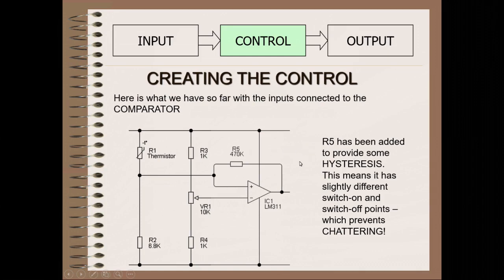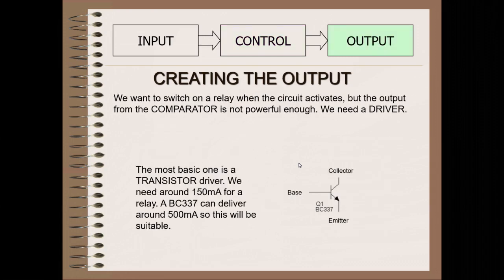R5 has been added to provide for hysteresis. It means that it has slightly different switch on and switch off points to prevent chattering. So if your switch on and switch off points are too close to each other, it would probably rapidly fluctuate between the on and off state, and that's undesirable, obviously. And so they try to differentiate the two points so that there is no chatter or rapid fluctuation of the control.